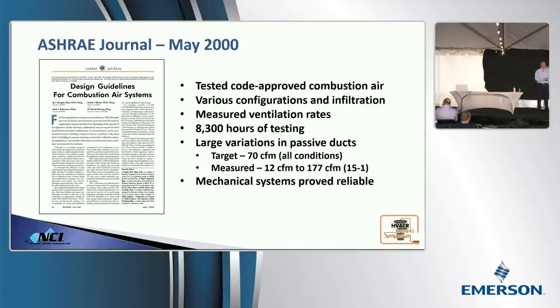They tested code-approved installations. They had dampers on them. Sometimes we've run into combustion air installations that are interlocked. The equipment comes on, dampers open up, right? They tested it both ways. Multiple configurations they tested this. They ran it from top to bottom. They heated the combustion air. They checked with different pressures. They checked at different outdoor conditions, barometric pressures, wind conditions. And they documented everything. Here's what they found. All these configurations had different ventilation rates, and none of them were consistent.